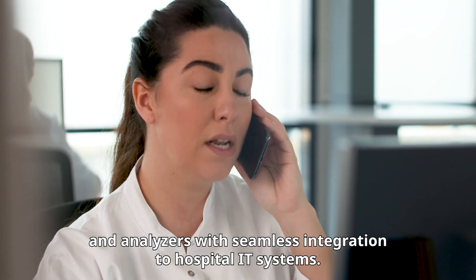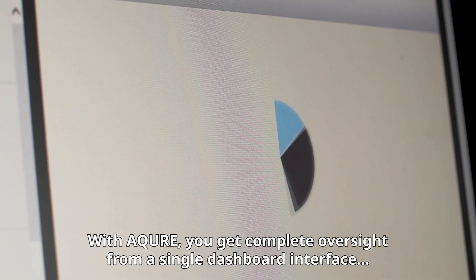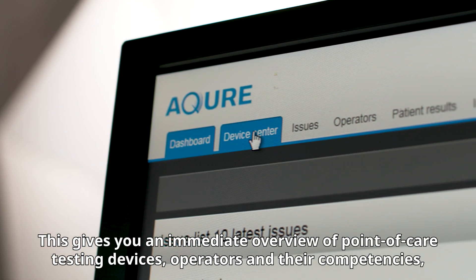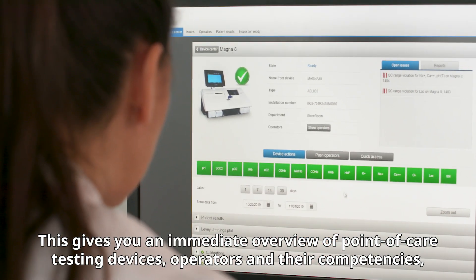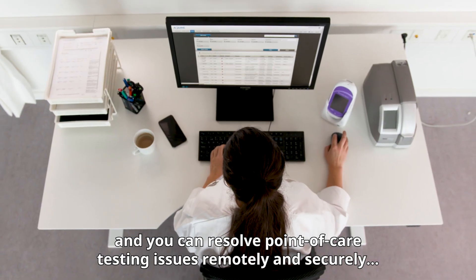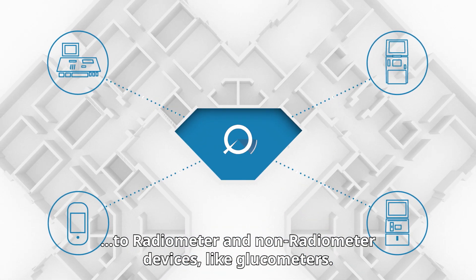With AQURE you get complete oversight from a single dashboard interface that can be customized to your needs. This gives you an immediate overview of point-of-care testing devices, operators, and their competencies, and you can resolve point-of-care testing issues remotely and securely through an open IT solution that offers connectivity to Radiometer and non-Radiometer devices like glucometers.